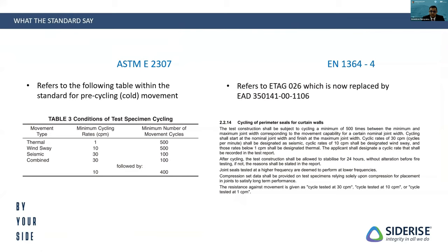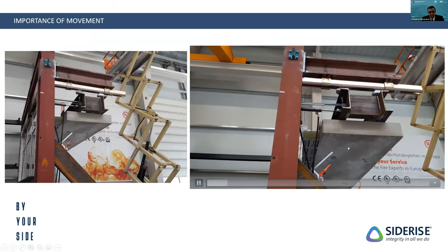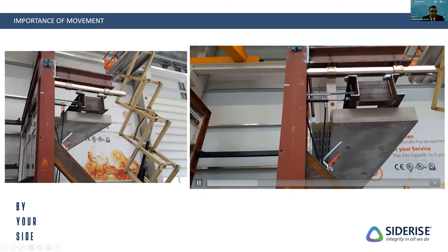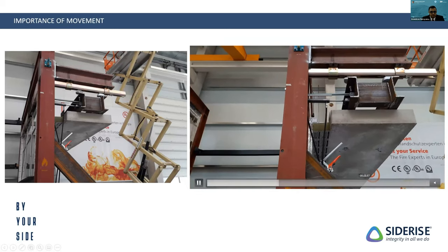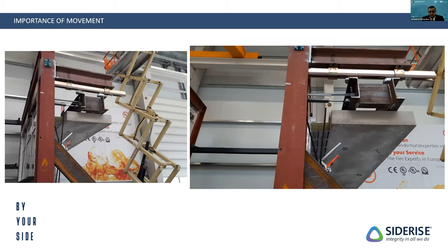These standards are important because, as the previous speaker noted, buildings experience movement — wind pressure and thermal movement on the floor slab. Products installed between the floor slab and the rear of the facade must accommodate movement when either the facade or the floor slab moves. Both standards require testing the material for cycling. On an ASTM standard, it is 100 cycles total; on an EN standard, you do 500 cycles at 30 cycles per minute. The same specimen, without dismantling or changing any material, is then tested for fire for the desired time period.